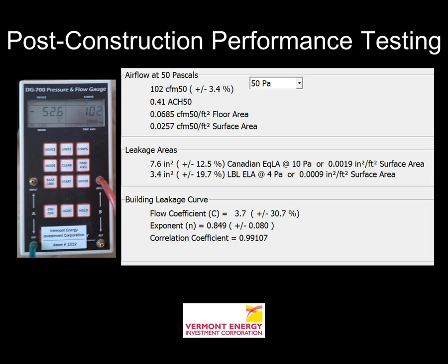As I said before, the building has to achieve 0.6 air changes per hour at 50 pascals. Here we are. This is the actual blower door test for our building. We hit 0.41 ACH50, or about 102 CFM at 50 pascals. A very, very low amount of leakage came through this envelope.